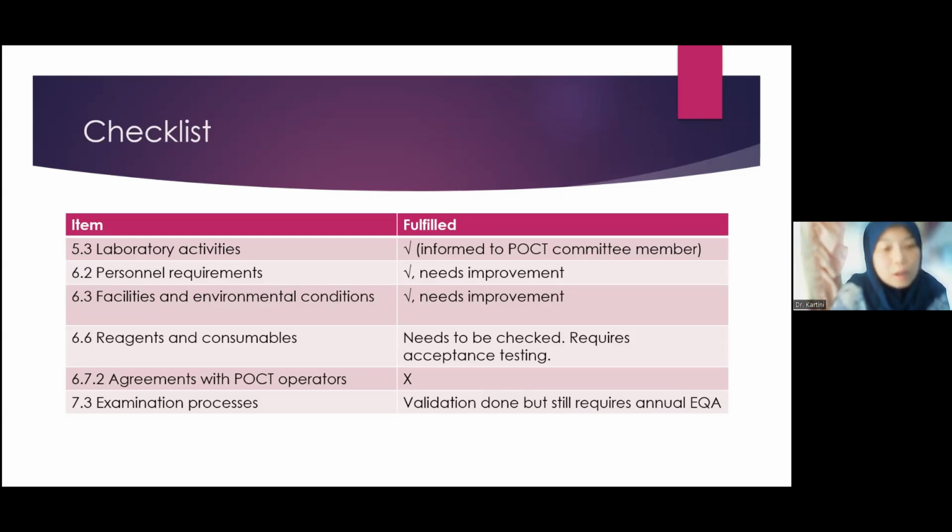And this follows to the next requirement, for reagents and consumables. There needs to be more checking done on how it's being kept, and also when the facility accepts the reagents from the laboratory, there needs to be acceptance testing, which has not been implemented yet. So far, we have not had any agreements since the 1990s with the POCT operators, and I was only informed about this like last month, 2 months ago.